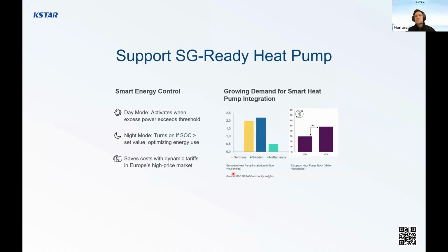SG ready is configurable. We have a day mode and a night mode. It activates when the excess power reaches a threshold. So if we export too much to the grid, we can decide to use that energy, for example, during the day when the price of electricity is relatively low. This time we can just use this energy to raise the temperature in the boiler, for example. It doesn't have to be the heat pump. It can be heating coils or something else that uses the energy.